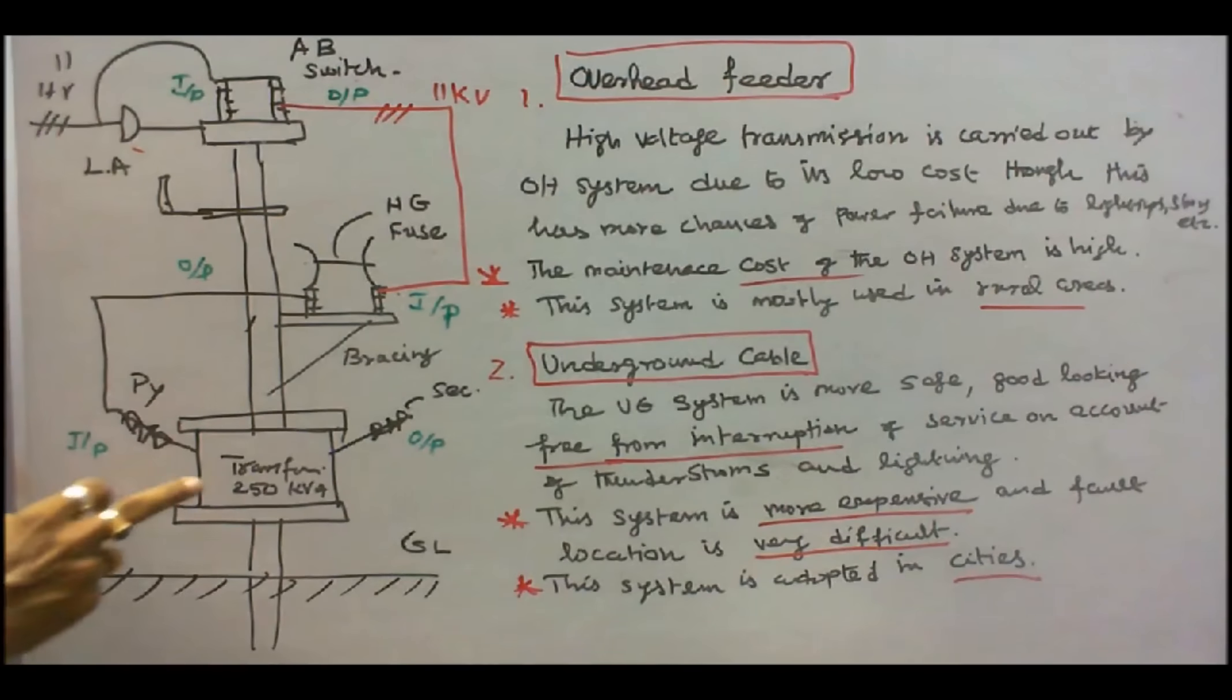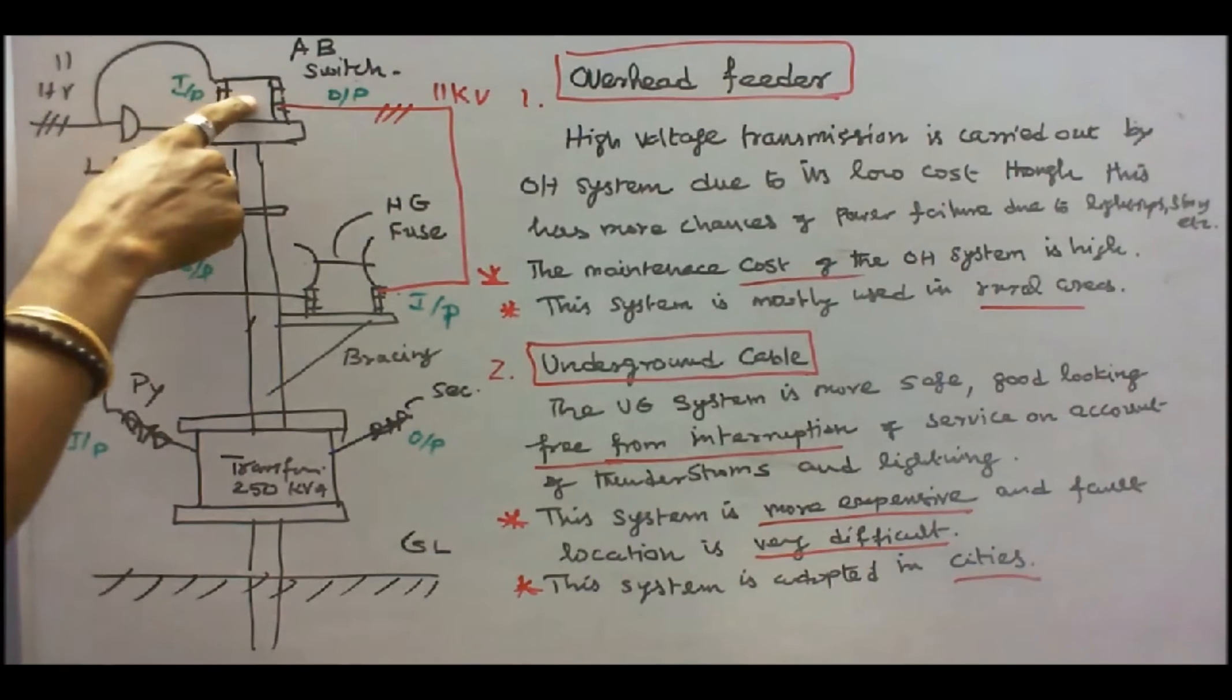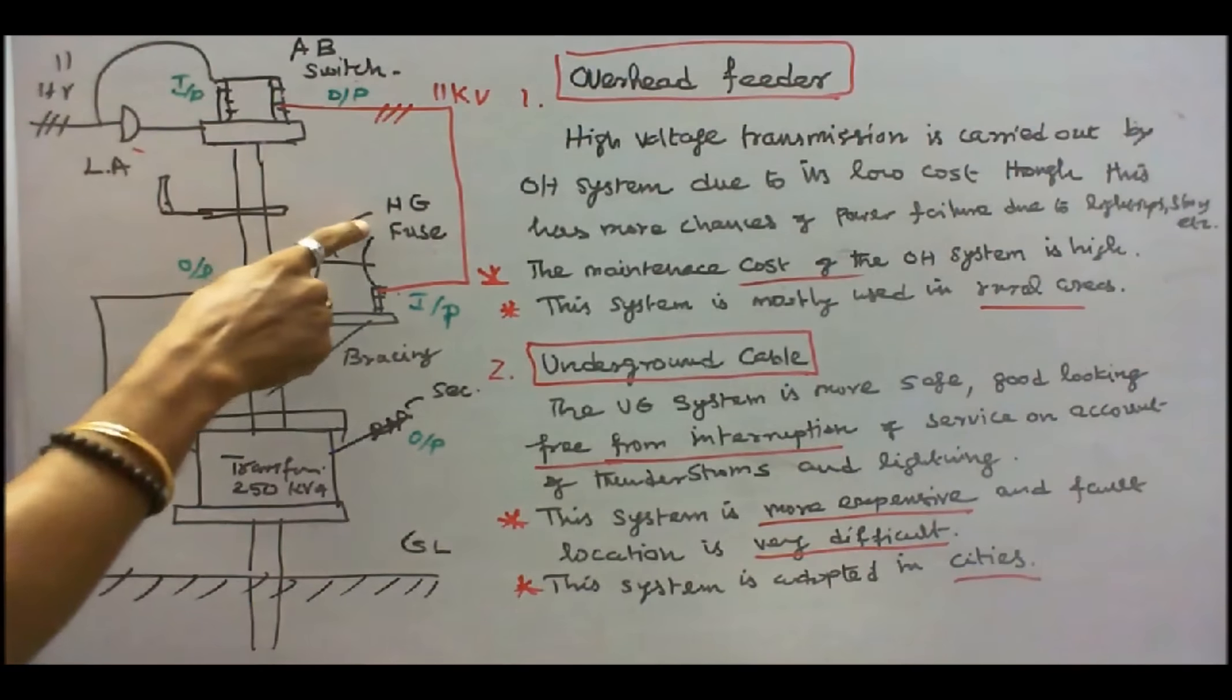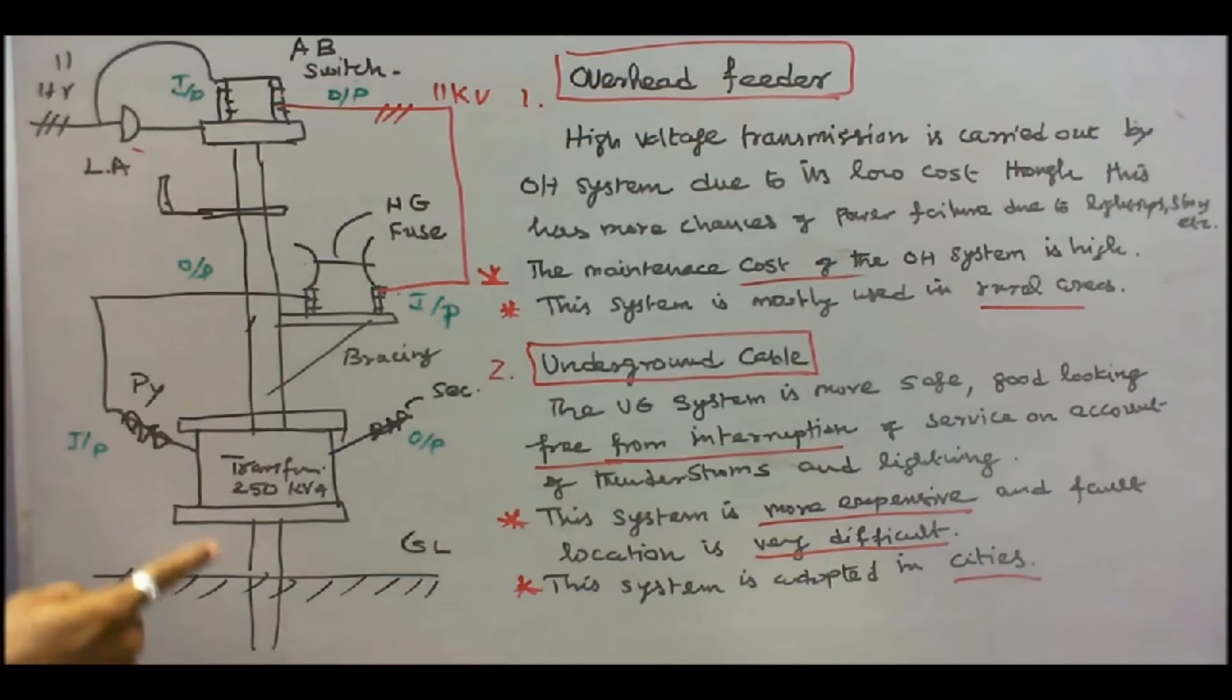Here, a 250 transformer is installed on a 2-pole structure. Here, this is the incoming 11KV line, 11,000 volts. This is the air brake switch. This is the horn gap fuse unit. And this is the transformer primary. This is the transformer secondary.